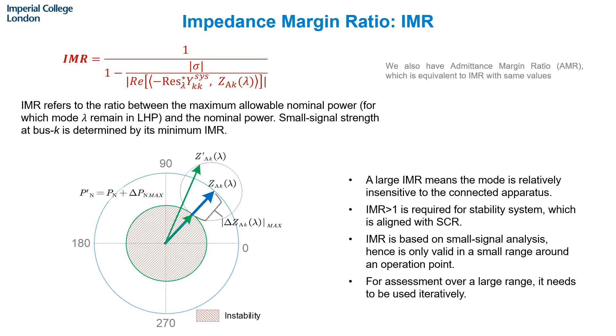It should also be noted that IMR is based on small signal analysis, hence it is only valid within a small range around an operation point. If you want to do it over a larger range, you need to do it in an iterative way. So how do we use IMR in practice? In the first case, consider that you are going to connect a new IBR to the system. At that point, you can extract the information of the network impedance spectrum, which is actually the Thevenin impedance spectrum.